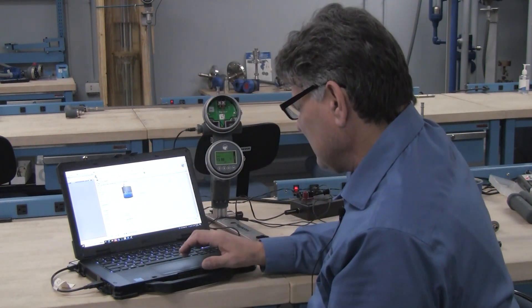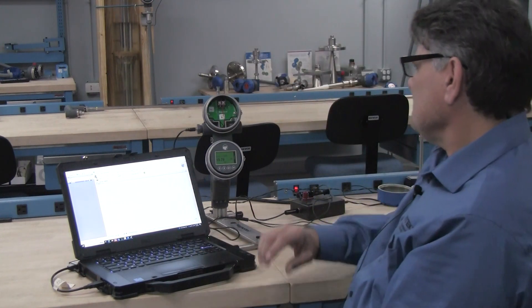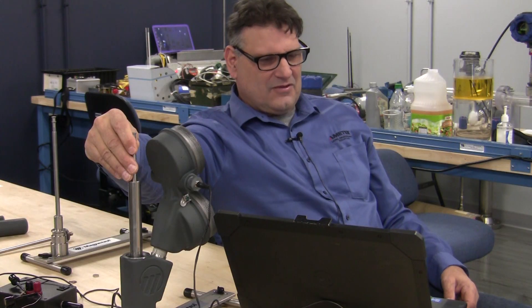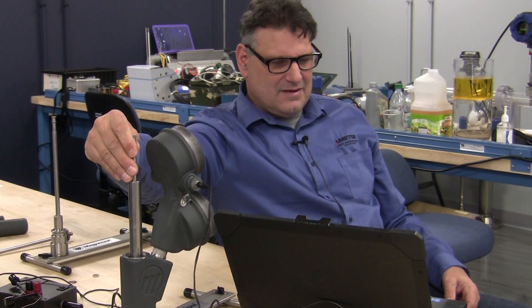I have now set this up where it will track the LVDT movement. So I'm slowly moving the LVDT down, which is simulating a lower level. And you can see on my screen, the transmitter is responding to that. And then likewise, I'll just lift it back up a little bit and you'll see it respond.